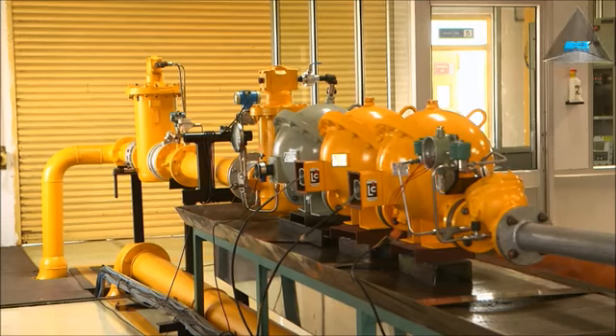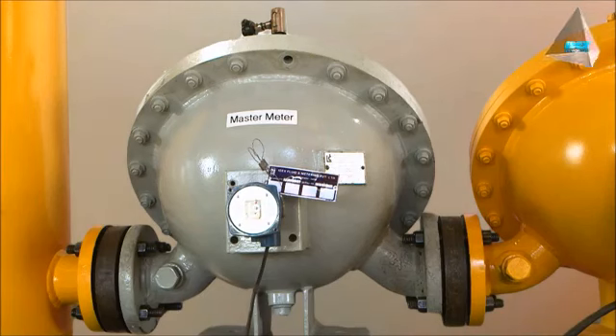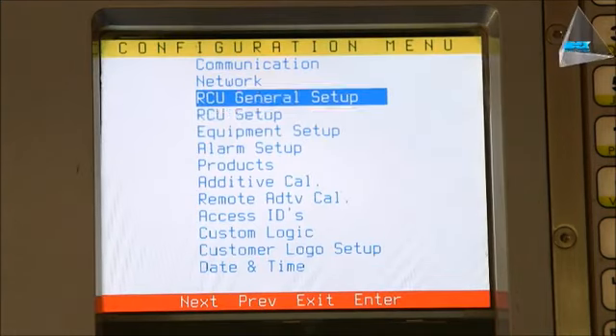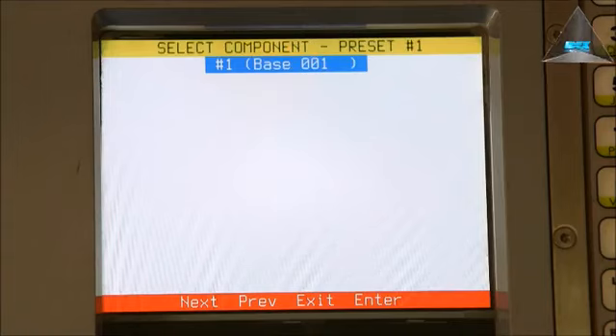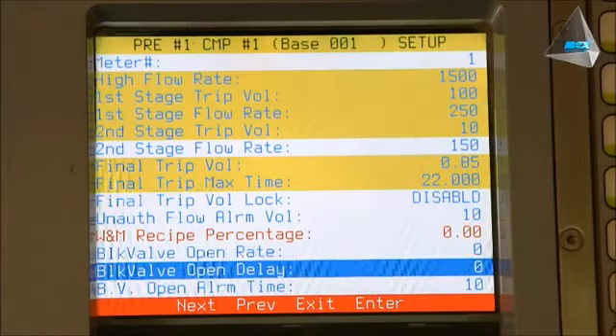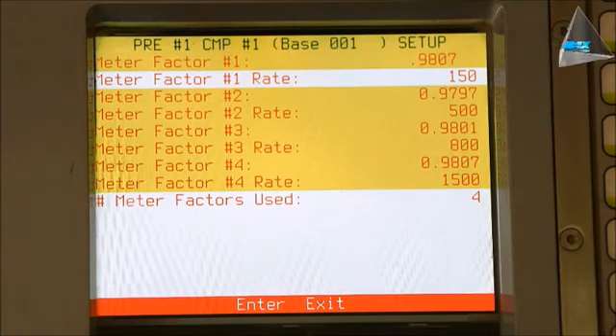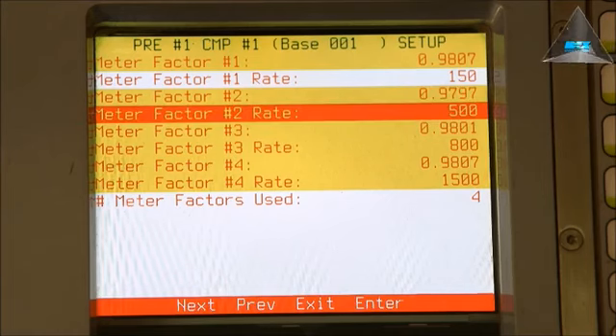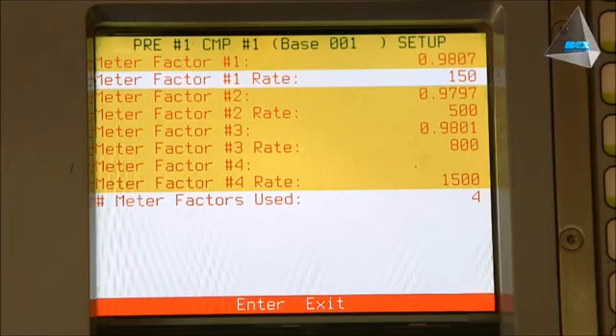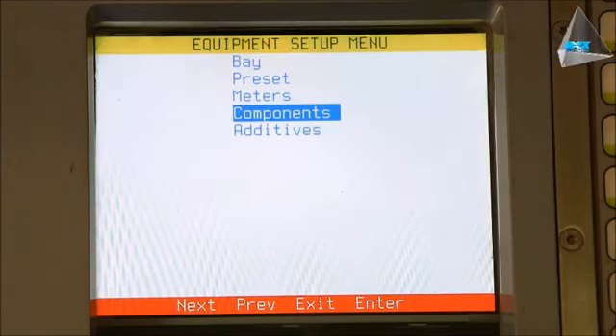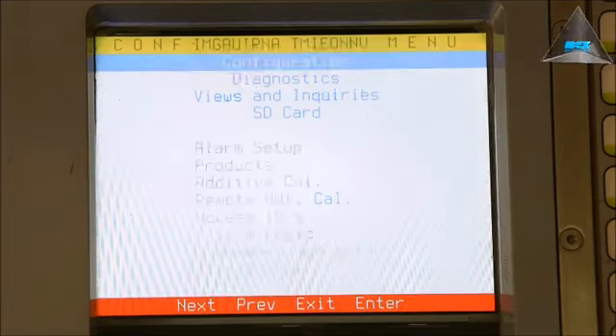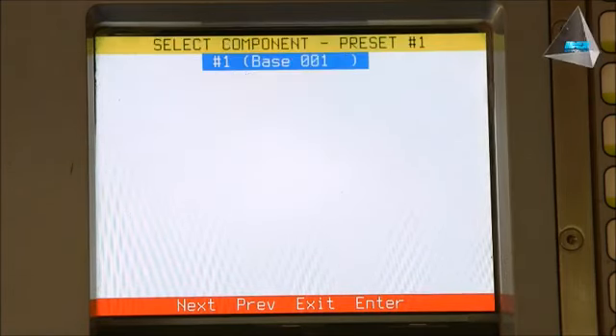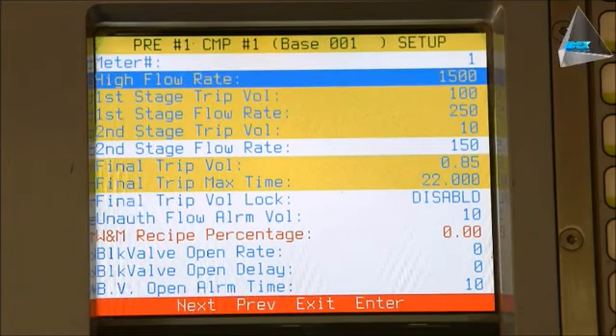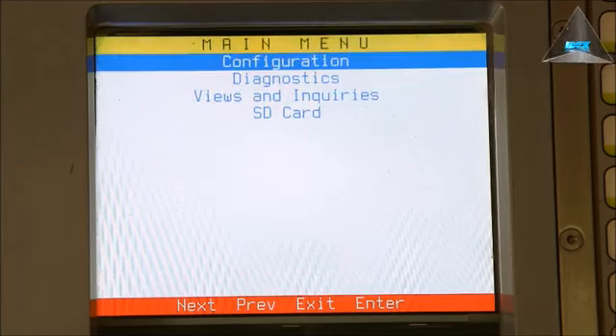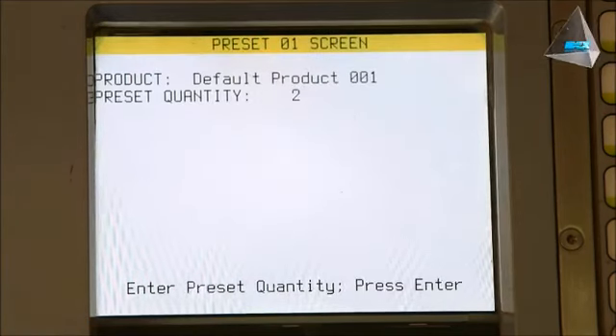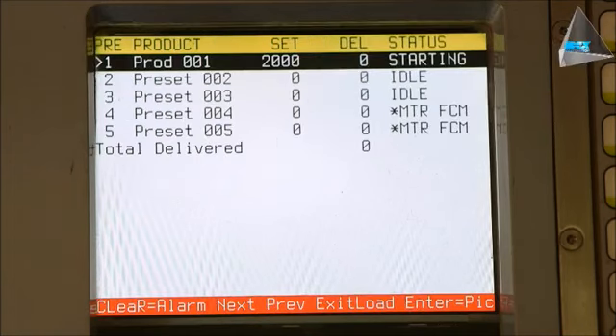The meter under test will be installed on the IDEX fluid and metering test bench against the master meter. Feed the K factors of the master in the batch controller for the master meter. A flow rate of 1500 LPM will be set using the master meter with the batch controller. At 1500 LPM, 3 readings of the test meters against the master meter are recorded.